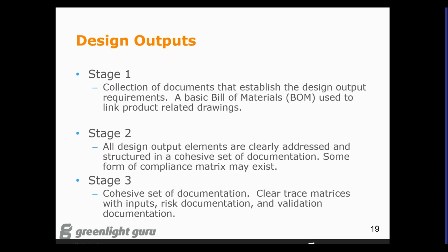A lot of times, whether it's going back to companies I've worked for or gone in and audited, the question is how do you demonstrate your design outputs meet your design inputs, and you pull in some knowledgeable subject matter expert and one of the key designers, and they say, oh, okay, this input is covered over here on this drawing or this specification, and they're able to verbally demonstrate those links.